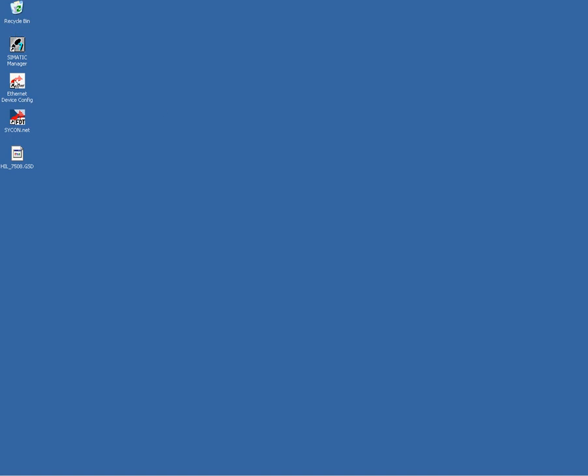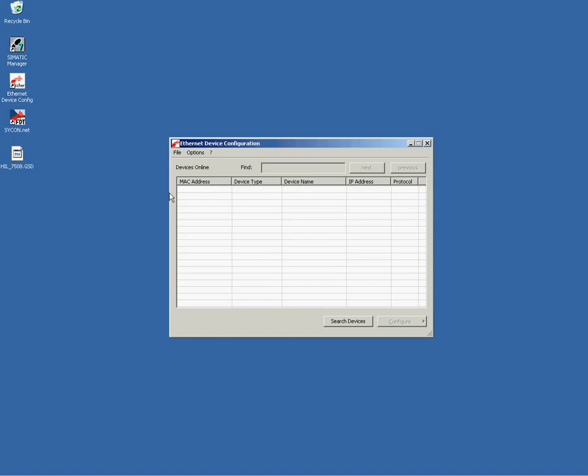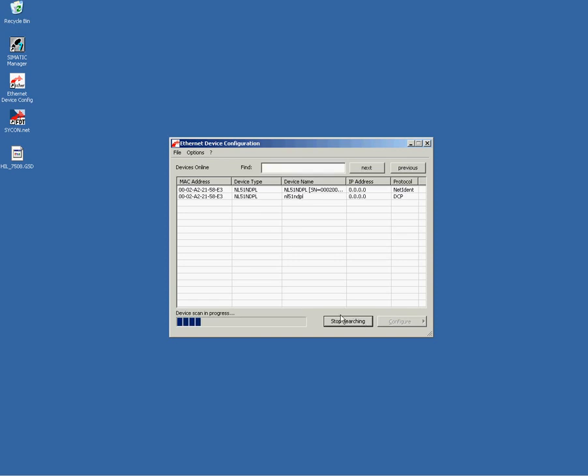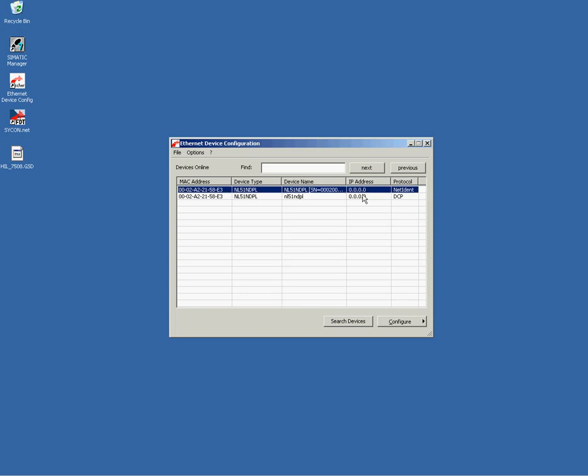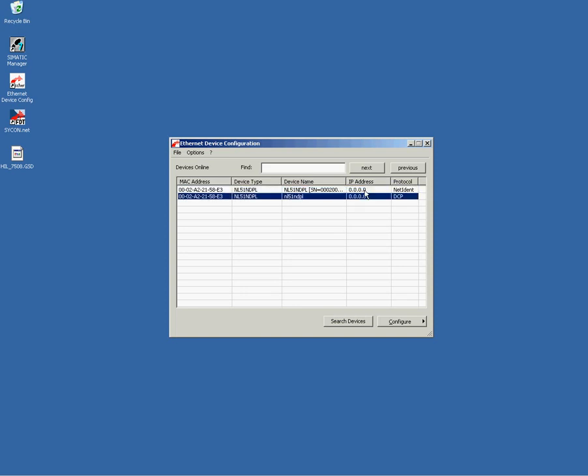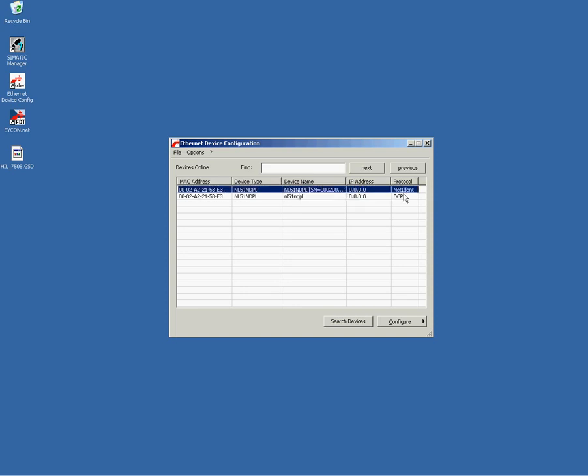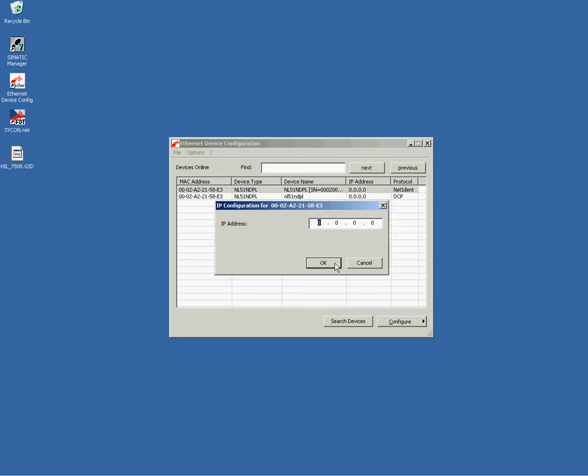Now let us start the commissioning. The very first utility you have to use is the Ethernet device utility. This program scans for Hilscher devices via broadcast messages. So press the scan button and you see here, the program has found my Netlink device connected to my local subnet.